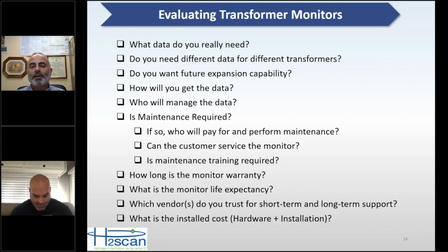And for certain transformers, you may want a $100,000 or $150,000 monitoring system, because it's going to be worth it to have that peace of mind that there's no issues in your transformer. But of course, as you get to smaller transformers, there's no way to justify that. So do you need different data for different transformers? How are you going to get the data? Who's going to manage that data?